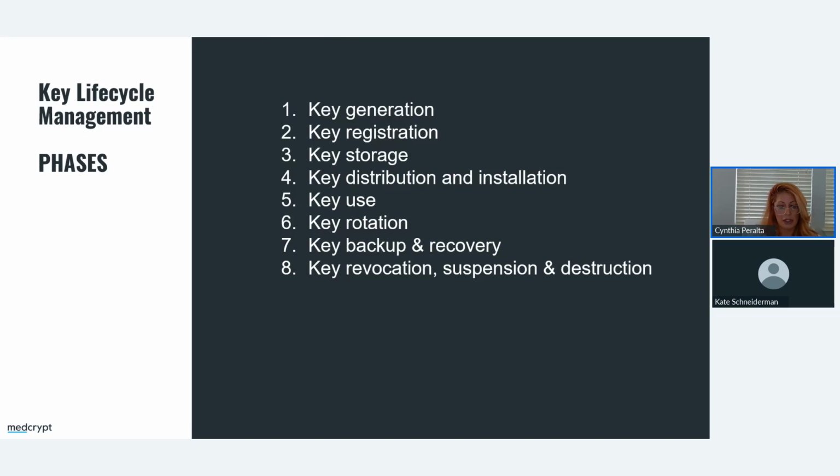Defining and enforcing the key management policies affects every stage of the key management lifecycle within the medical devices and those interconnecting environments and systems, as mentioned earlier. Each encryption key or group of keys needs to be governed by an individual key usage policy defining which medical device or group of devices or even types of applications can request it and what operations that device or application can actually perform. So for example, encrypt, decrypt, or sign.